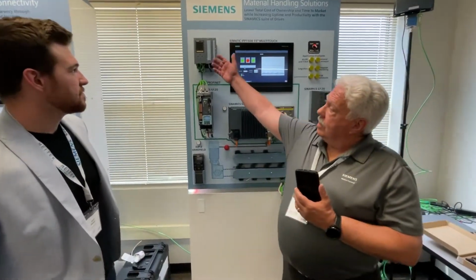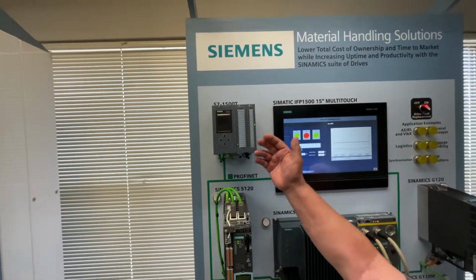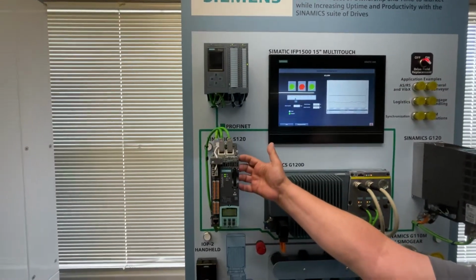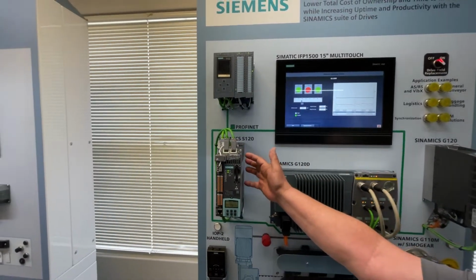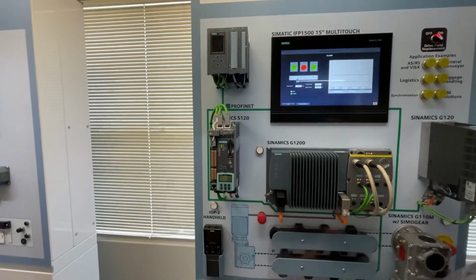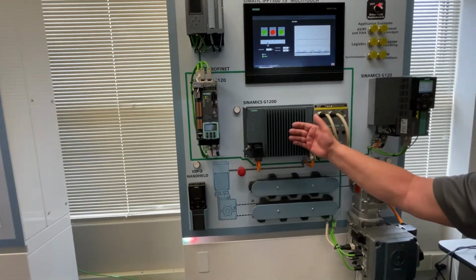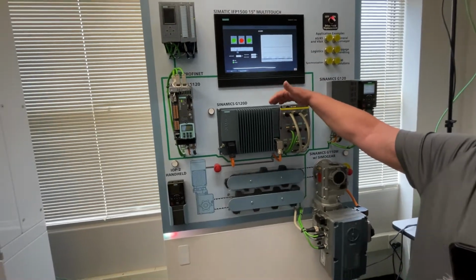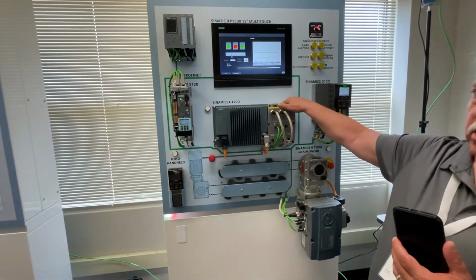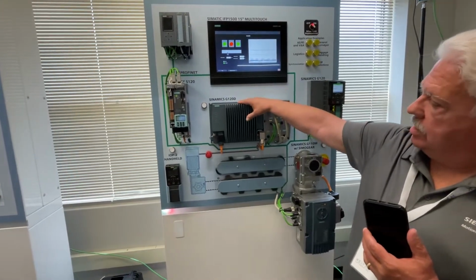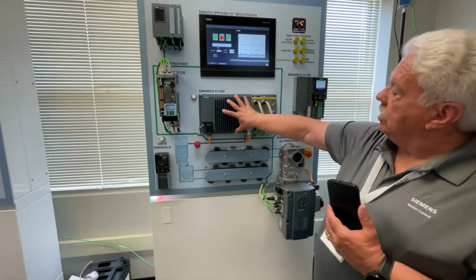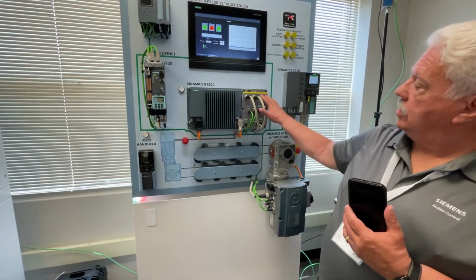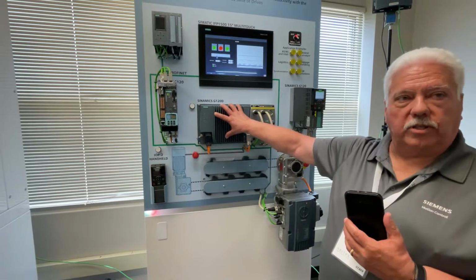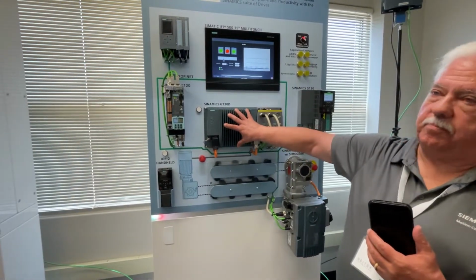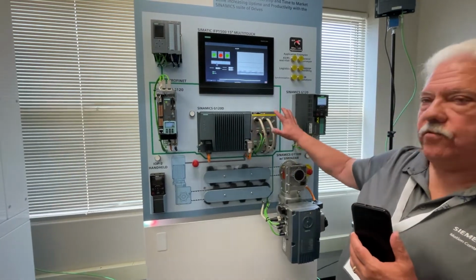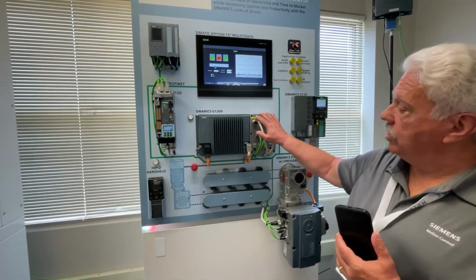In this case, we have an S7-1500 PLC with remote I/O, high-end motion control drive and motion controller. In this case, we have a field-mountable drive. This is a modular drive, meaning that the silver piece is the control unit. The dark gray piece is a power conversion section. The reason these become separate is because we can utilize different types of control modules to control this power module. The power module is 90% of the failures in the field will always be in one of these. Very quick to get one drive that goes down, up and running again in the field.